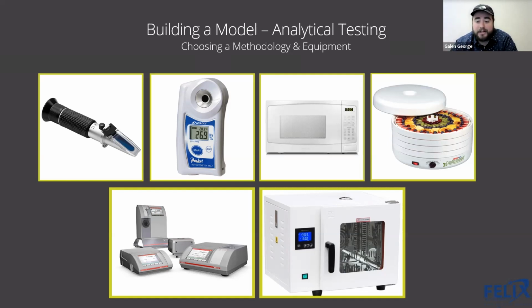A much more controlled environment and a lot more accurate at the end of the day when you're performing your testing. But again, like with the Anton Paar laboratory grade refractometers, it's a more expensive route. So if you are not going to be able to invest in higher grade equipment to do this testing, you need to invest in some sort of quality control and active monitoring to ensure that the equipment is performing how it's supposed to. At the very minimum, you should be doing that. So it's really still going to come down to money, but at the end of the day, it's always going to be a better option to use the higher quality equipment to perform your analytical testing.